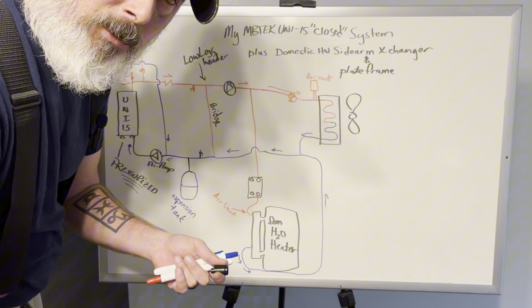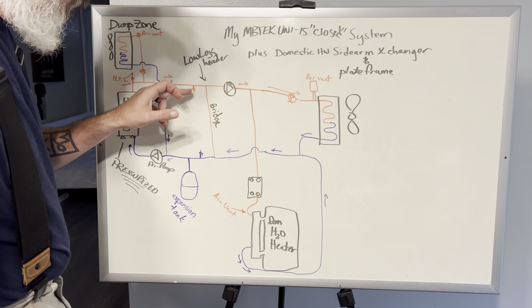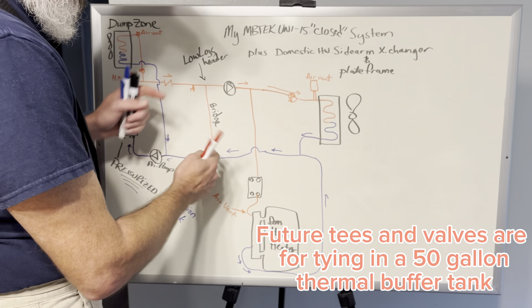Right here at the boiler is a high pressure safety, a pressure relief. That one is set at 25 pounds, so it will open if the pressure in the system, or at least as it's experiencing right there, gets above that. If you look at just this portion for now, this comes out, goes up under the ground to my house, and as it comes up under the house, I've got a check valve, a T and a 1-inch valve. That's for a future use, and I'll explain that in a second. Then I have a low loss header, shown very big here relatively speaking.